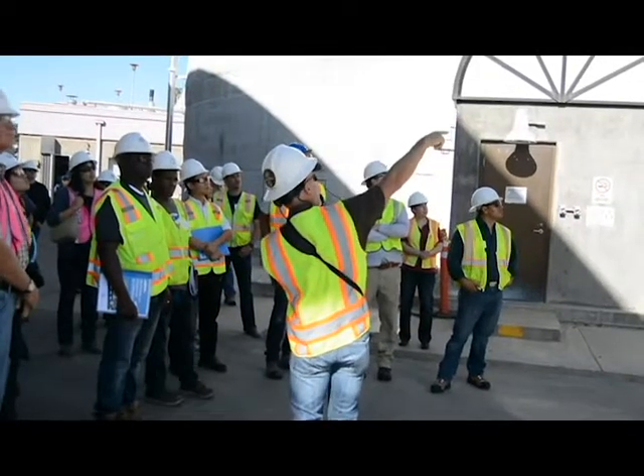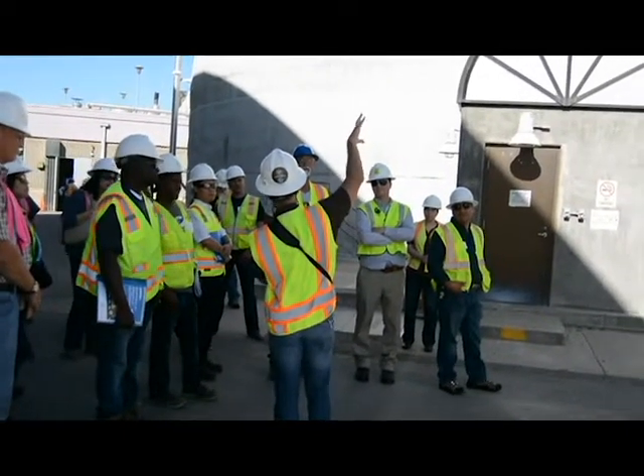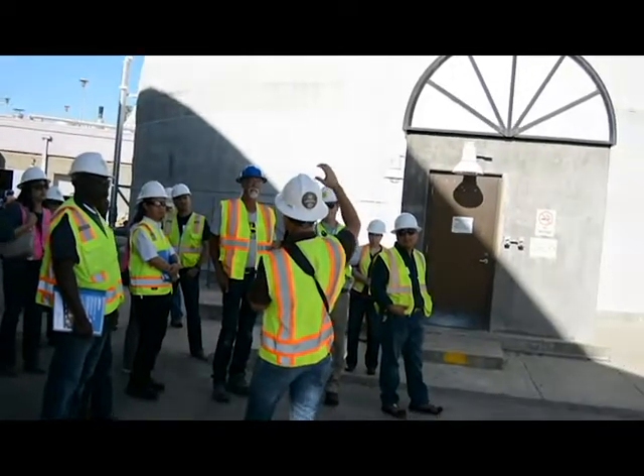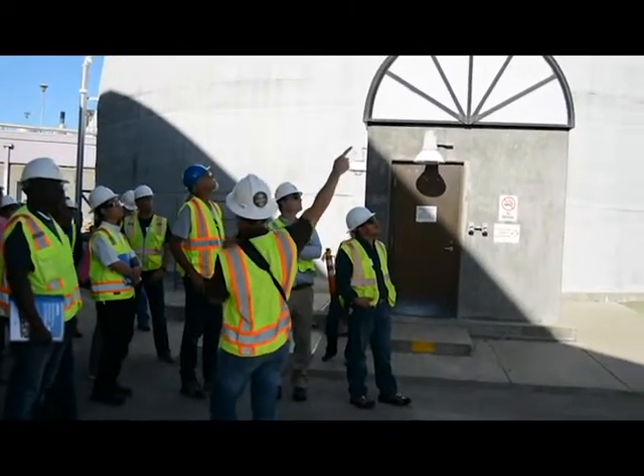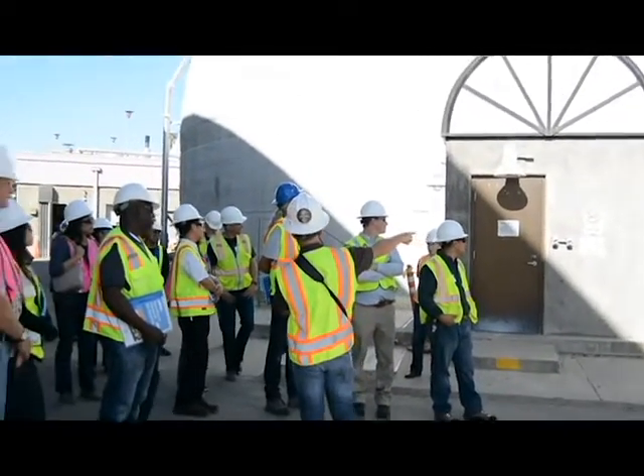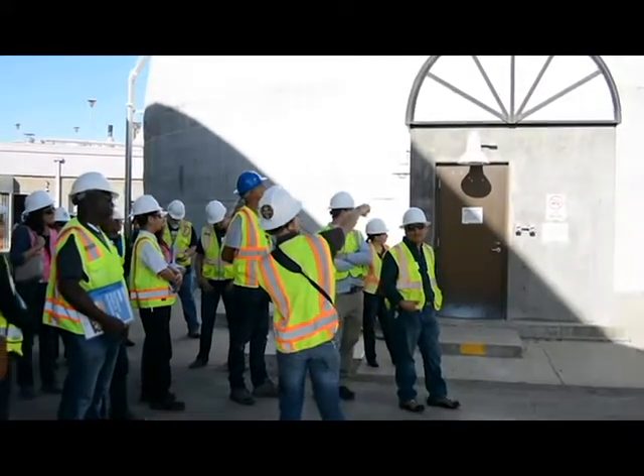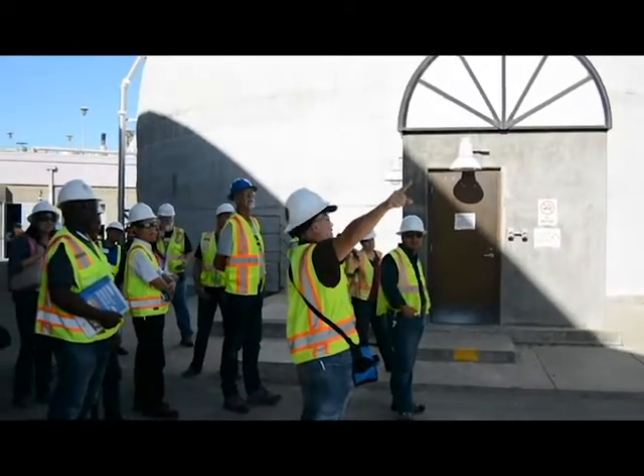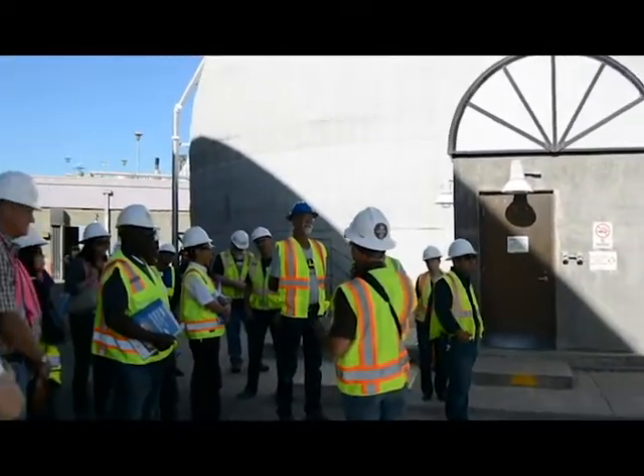This is a double-liner structure. The blowers over here are sucking air out of the envelope in between, which creates a little pressure so the bag inflates on the inside. When we need to use it, the blowers turn the other way and create slightly higher pressure which squeezes the bag down inside. So this always looks the same on the outside. We had lots of issues with this — air was bouncing off the digester right here and reverberating inside. We had to put a buffer on it because it was bouncing and there was a receptor neighbor about a mile away, causing huge problems in the city. But that's all taken care of now.